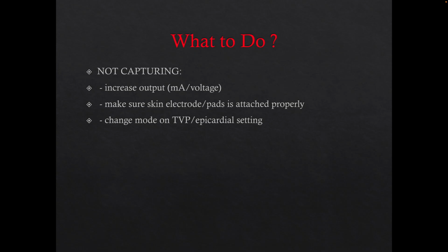So when you have capture, if you lose capture and need to increase your output, if your output is set at 5, go up to 6, 7, 8, or go backwards. The leads are different, one goes up to 20, one goes up to 25 MA. Start a little higher, maybe at 15. Oh, it captures, 14, 13, 12, keep going down. Wherever they lose capture, you want to go a little bit above that.